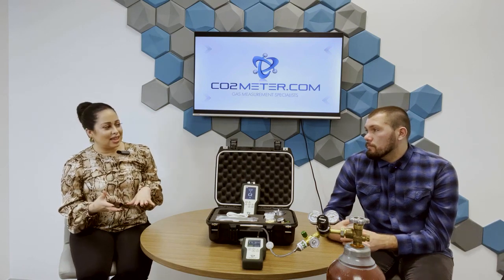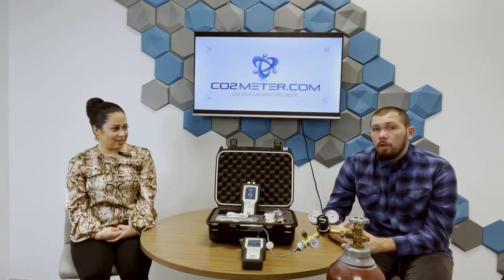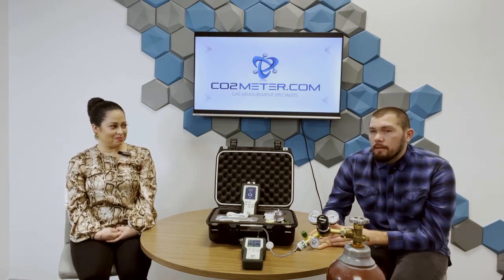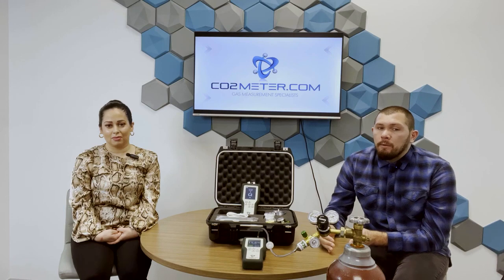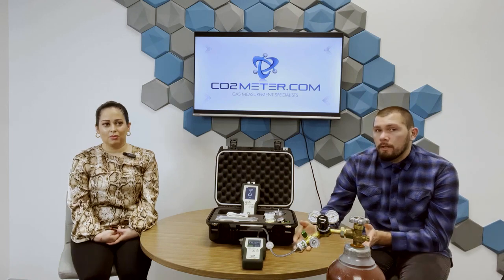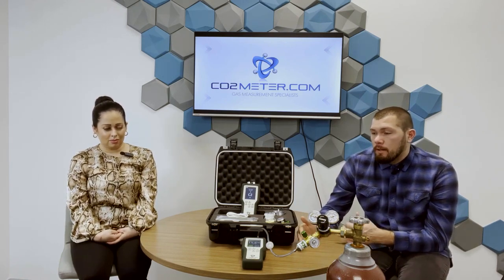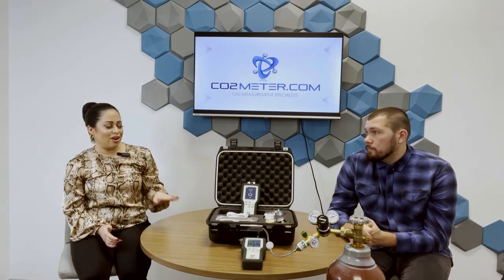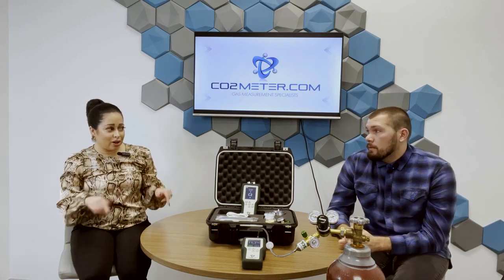But what about competition? That's something I myself as an end user want to look at. What else is out there in devices like these? This device is filling a large hole in the market. There isn't really anything that competes with the 1650 currently in the US market. Something that meets that AWS standard and measures 0 to 100% CO2, hitting the entire welding gas, CO2 blend welding gas measurement range, is something really new on the market in the US. So to reiterate, no other device can currently meet AWS standards. Nothing out there does what this device does.